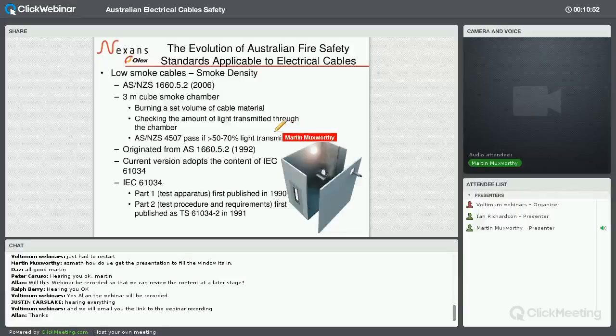For low smoke cables, typically you need to have at least 50 to 70% of light transmitted through that chamber when the sample is burnt. Again, a lot of these standards originate from quite a while back, AS1660 Part 5, Part 2, 1992. And I think what I'm also demonstrating is that our Australian standards evolved predominantly from the IEC standards, and in this particular case IEC 61034, and they date back to the early 1990s, for example.